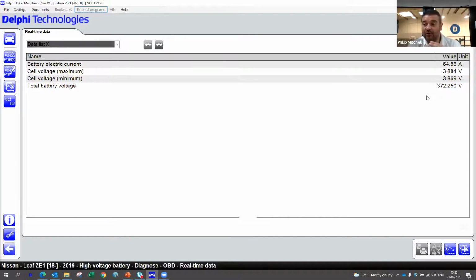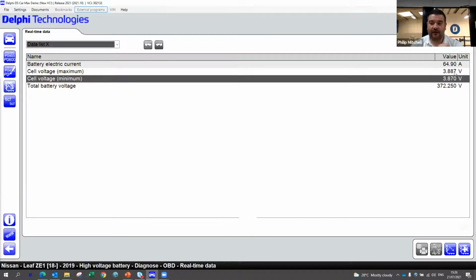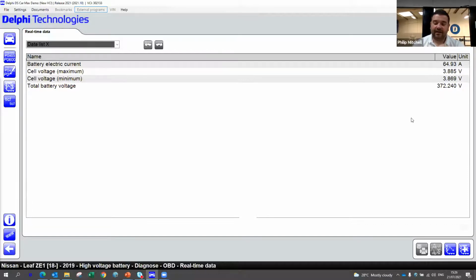So I'm noticing at the moment that we're about 869 and 886, so on average we're about a 15 millivolt difference between that number and that number. Now generally, what gives us areas of concern is if it's around about 35 to 50 millivolt. That covers most manufacturers, not all, but a good proportion.